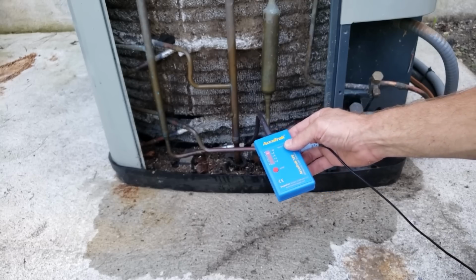That's a nice tool. There's a lot of tools that you can use, so you just want to make sure that it's one that's for that correct refrigerant. Some different refrigerant leak detectors are made for specific types. If it's a HCFC versus a HFC, it just depends on what kind. Anyway, so definitely, if you don't find a leak when you recover the refrigerant charge, then you're going to have to do that whole process.